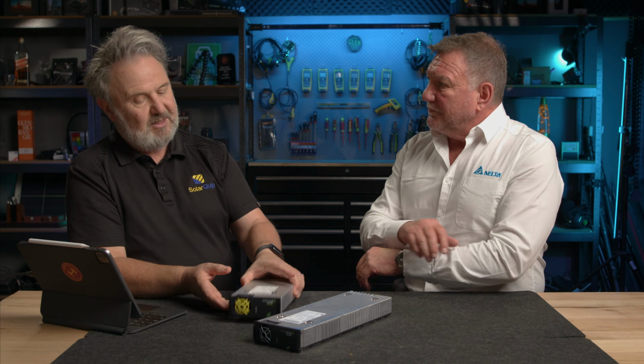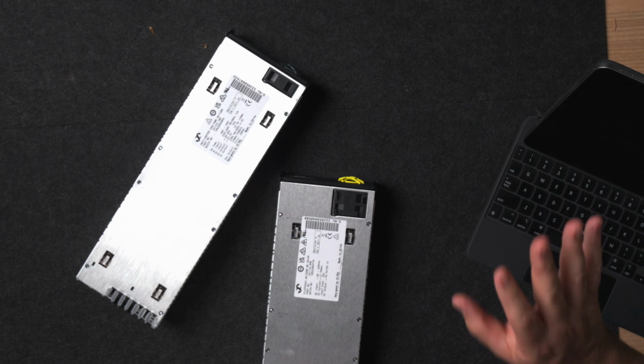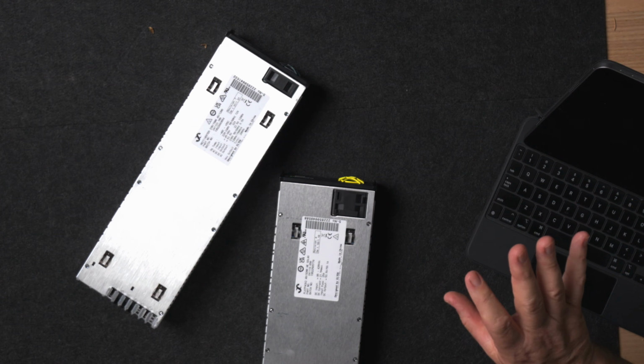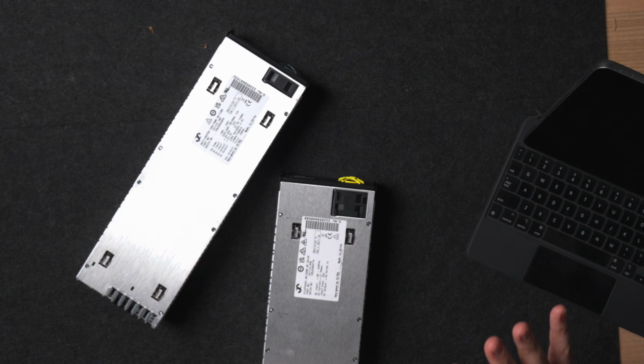So these solar charge modules give you another advantage over typical AC coupled systems. With AC coupled systems, you've got to match your AC solar inverter to your AC battery inverter - they've got a one-to-one relationship. But often you might have an energy demand that's high but a power demand which is low. Telco's a perfect example: a constant power rating but a lot of kilowatt hours per day.